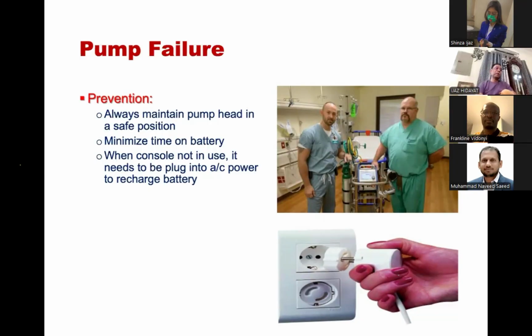We have different consoles where the pump head is different and the oxygenator is a separate part. In some consoles the pump head and the oxygenator are compact, like the Cardiohelp. But if you talk about the Centrimag, the Xenios, the Rotaflow or other devices, the pump head is separate from the oxygenator. So we make sure that the pump head is secure and in a safe position. It should not disengage from the motor, so we have to make sure the pump head is in a safe position.